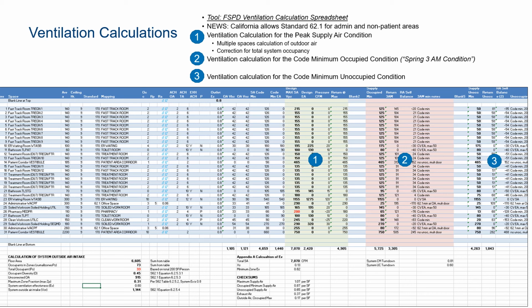In my mind, the ideal supply air temperature for that condition is 67 or 68 degrees, where you only have 2 or 3 degrees delta T in the space. But you need to look back at your load calculations. This is where those rogue zones will show their face, and this is where that med prep room can become a problem. And then finally, the third set of calcs you need to do is really for the rooms, and that is to know your unoccupied condition or the unoccupied opportunity.